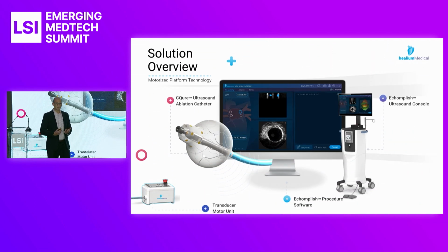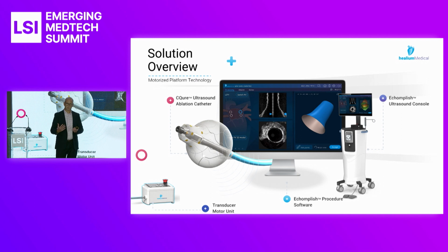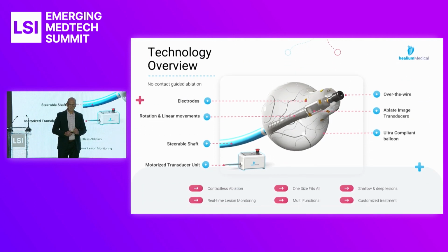So our solution is different. We use a different energy modality to create the lesion effectively. We use ultrasound, and the main building blocks of our technology are an ultrasound console, procedure software, a transducer motorized unit, and an ablation catheter. The way it works is that the ablation catheter is connected to a motorized unit. The transducer that emits the energy is surrounded by a balloon just to mechanically position the catheter inside the pulmonary vein, and we have surface electrodes to monitor the electrical signal throughout the procedure.